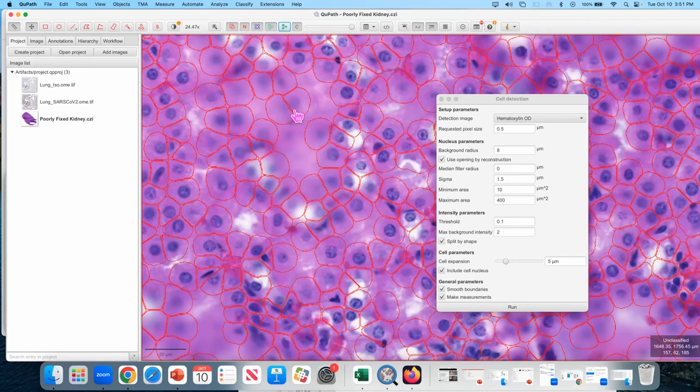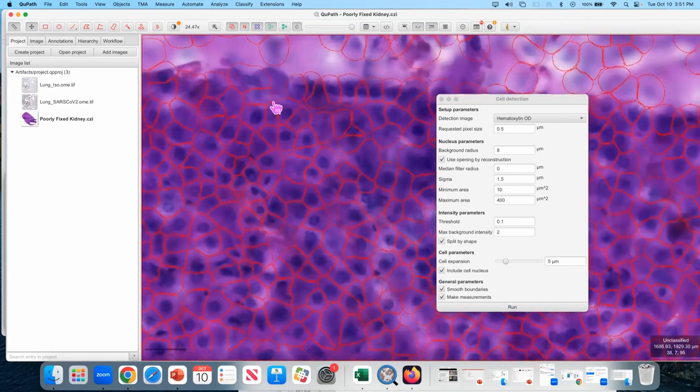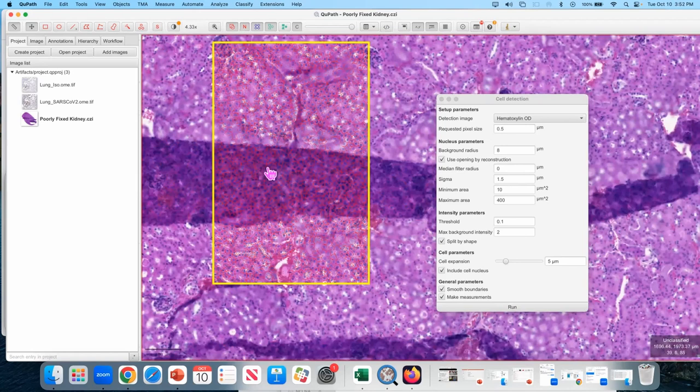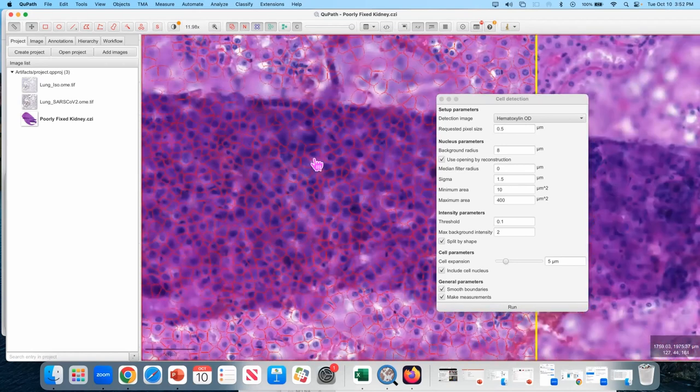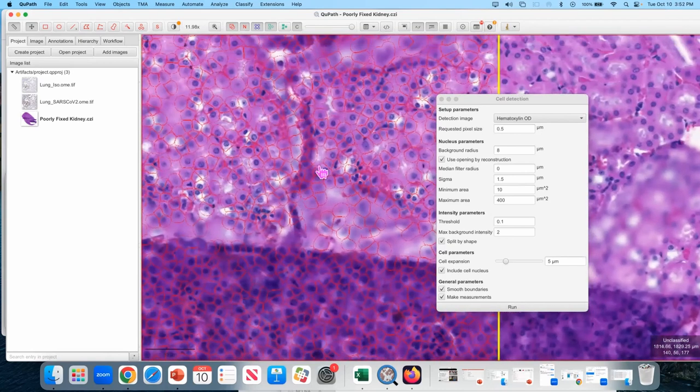And when a slide scanner scans an image, it scans something that looks like a dome, and that dome makes it impossible to focus on it. There are ways to go around it, but the best is to start with a well-made sample. And when you have a really bad fold, there are gonna be some cells that are on the top, some cells that are on the bottom, and it's gonna look like that.